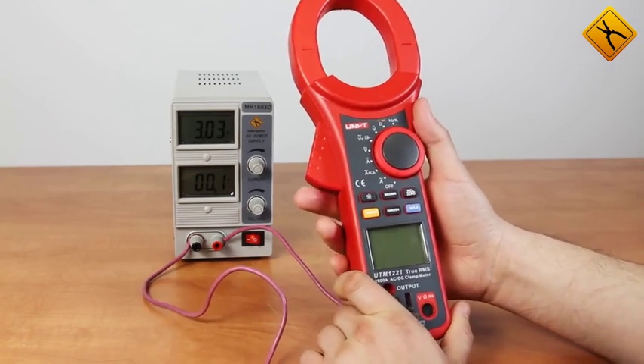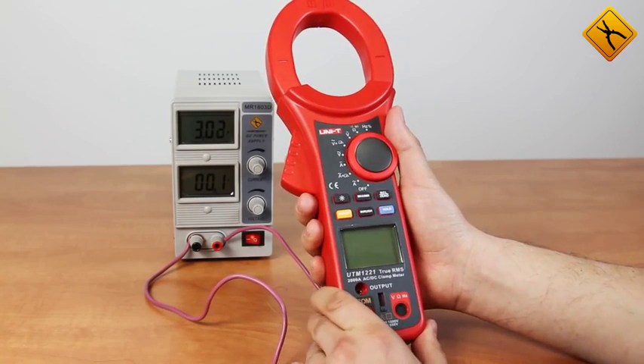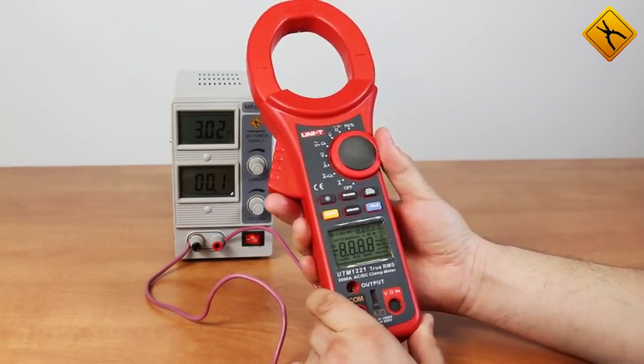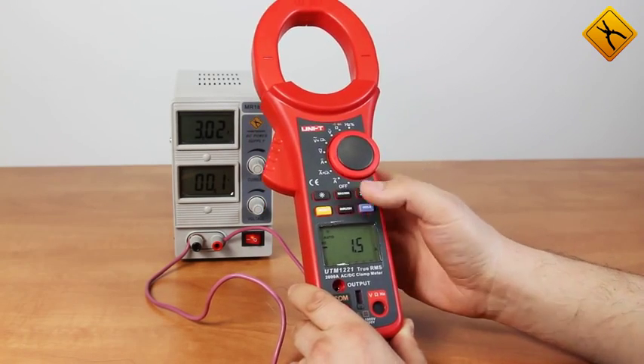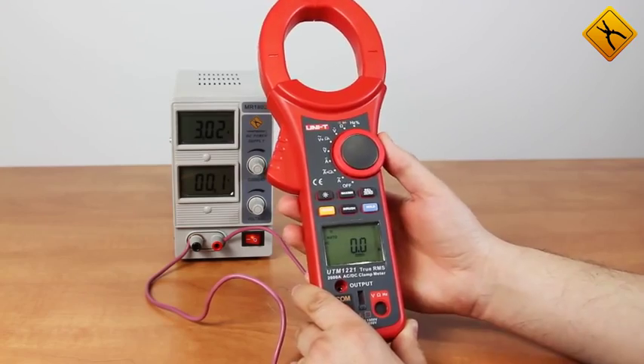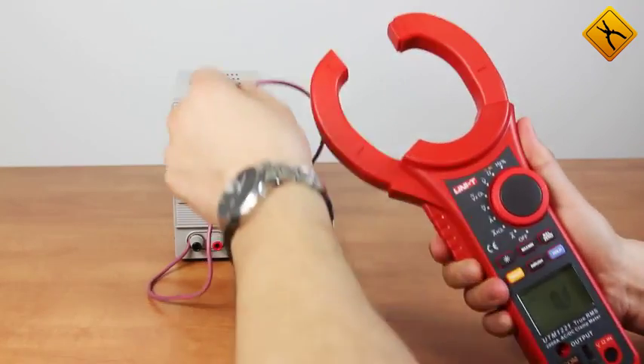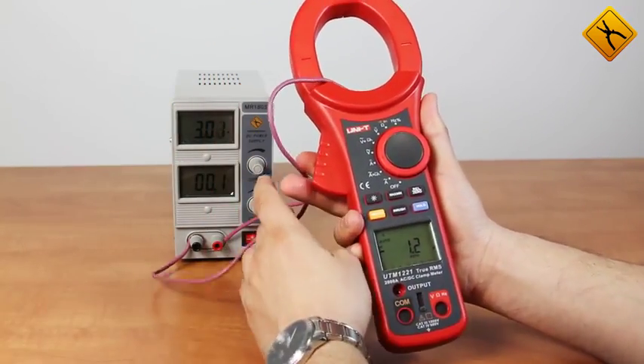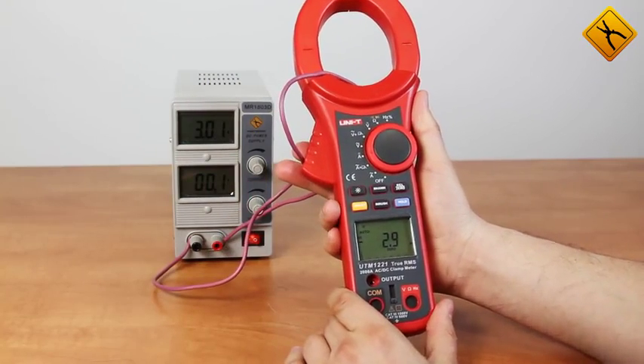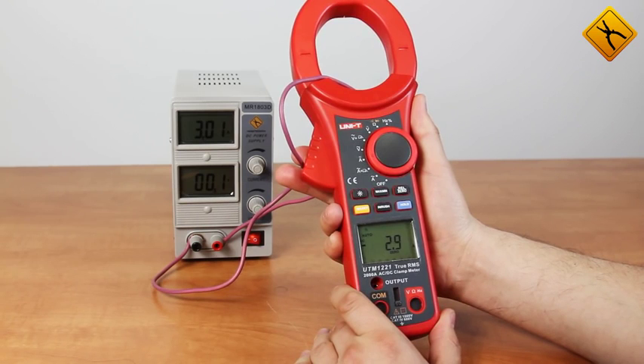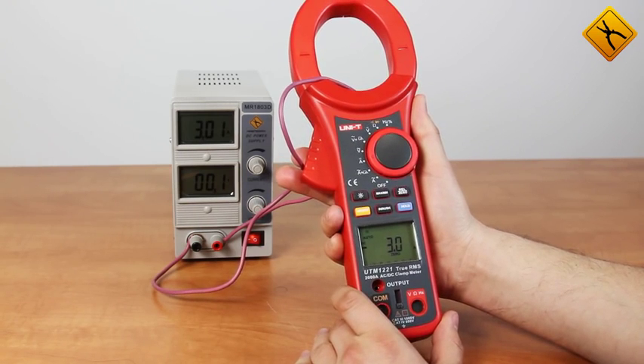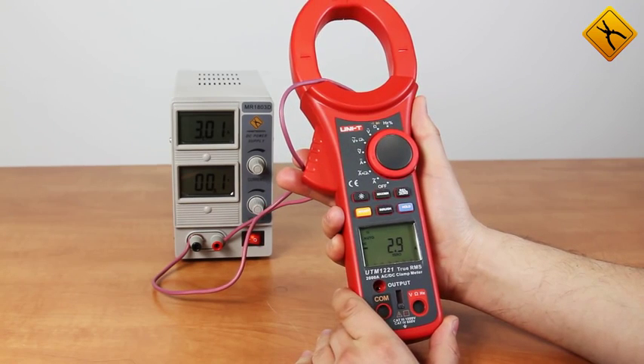Now, let's measure the DC current. Turn on the meter and switch to DC current measurement. Before starting the measurements, press the zero button to reset the display readings to zero. Start the measuring process. We may see a slight inaccuracy in the last order. Taking into account the DC current measuring range of 2000 Ampere, we consider the result excellent.